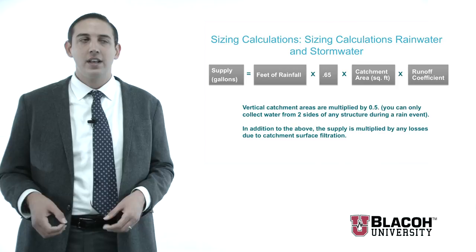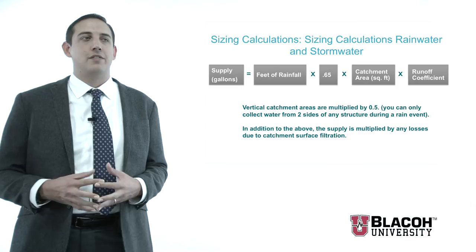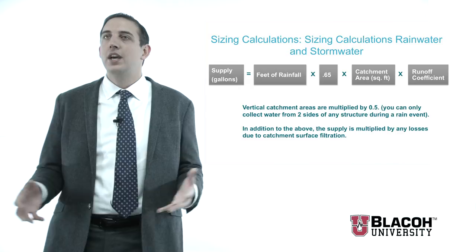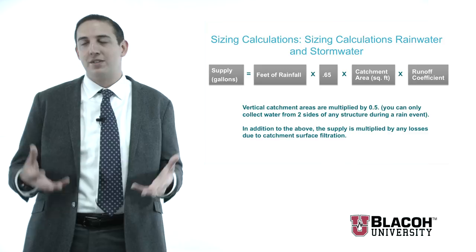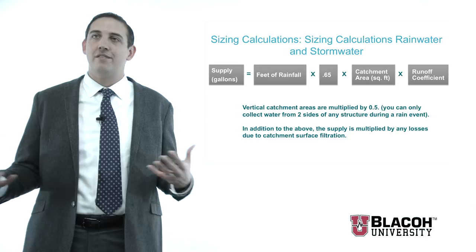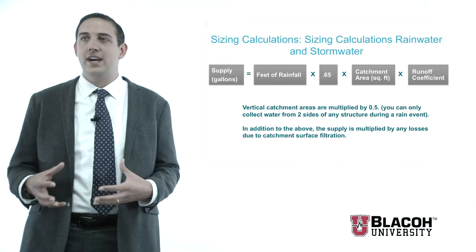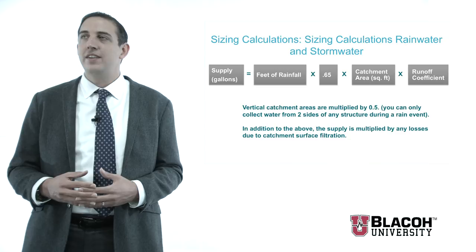The runoff coefficient comes into play during stormwater sizing. It dictates how much water you can lose based on what your surface area is. For a roof or even a parking lot, this number is generally one. If you're going to be catching off of another surface such as a sandy beach, you would end up with a coefficient of about 0.15 because you'd have so much more drainage. It should also be noted that you can only catch rainfall off of two sides of any vertical structure during any given precipitation event, so you can only account for about 50% of that overall vertical area.